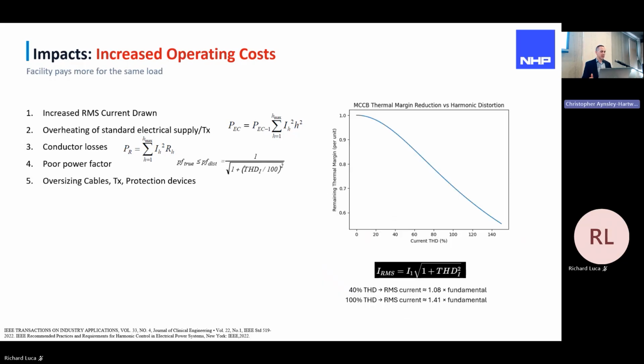With all that, points 1 to 4, we need to upsize now, oversizing cables, transformers, and protection devices to handle this increased wasted energy. And you can see the formula down the bottom: with a 40% THD in your plant, there's an 8% increase in RMS current. With 100% THD, there's a 41% increase in the RMS current.